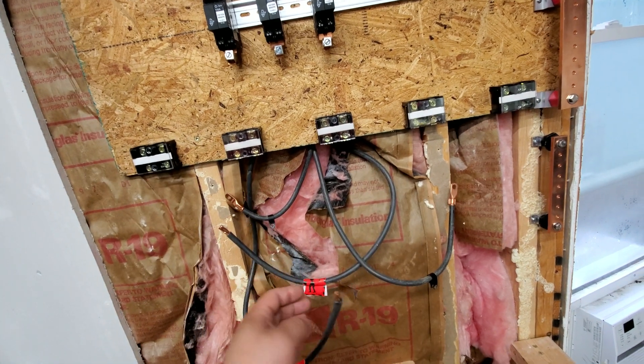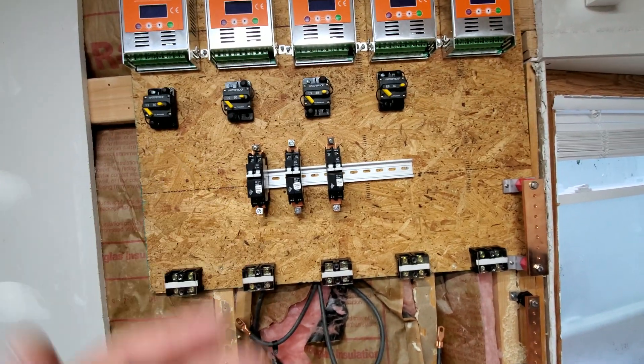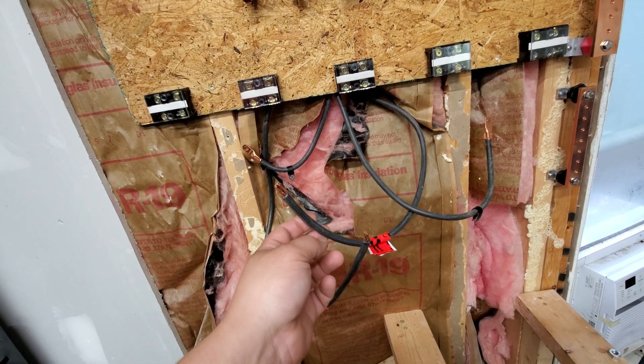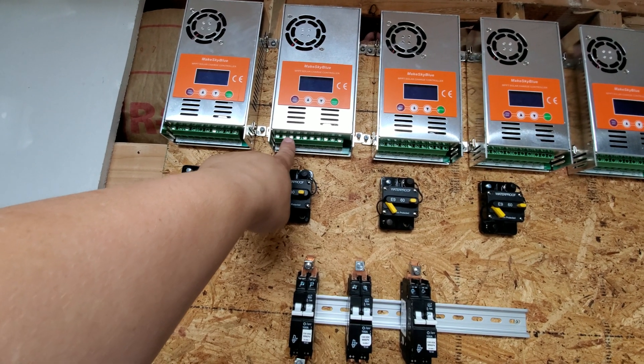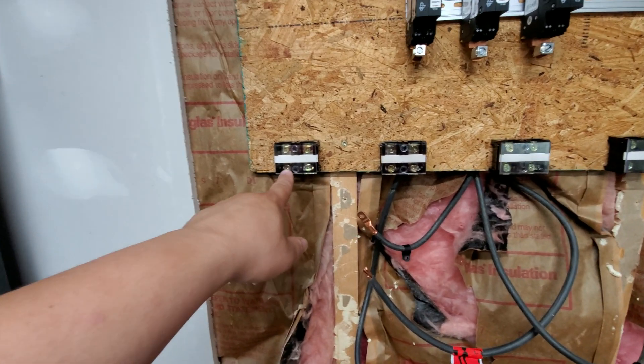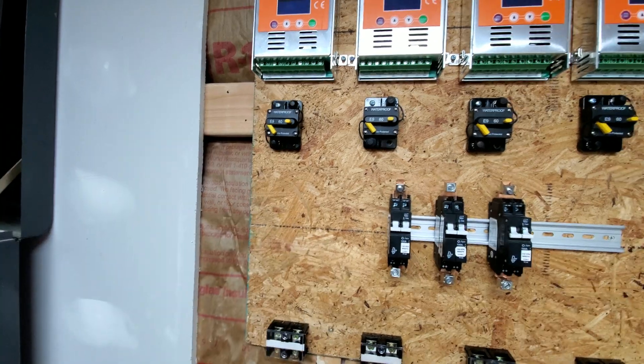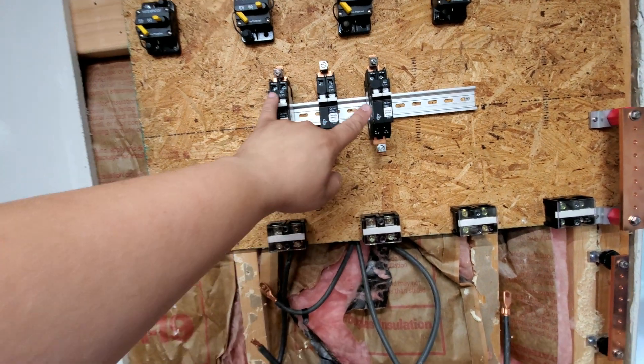The PV negative is going to come in through here, and the PV positive comes in here as well. There's going to be a total of five of these because I will have five separate arrays at approximately 2,200 watts each. The wiring coming through is 4-gauge USE wire, which is too big to fit into these connectors — they accept a maximum of 10 AWG. So I have to step down the wire size: the PV negative connects here, then two 10 AWG wires run up to the PV negative for all five charge controllers.